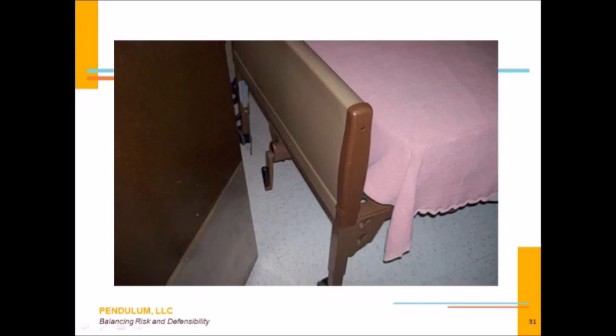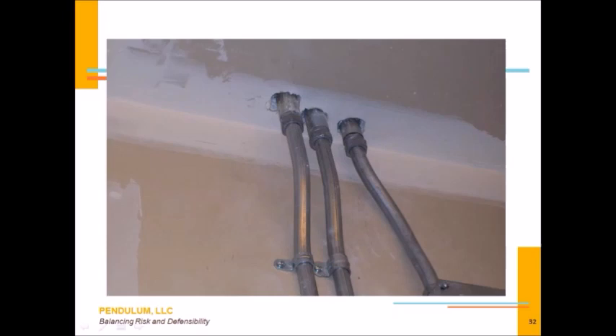Make sure all those items that are in the swing path to resident doors, to patient doors, or even to the cross corridor smoke and fire doors, there should be nothing within the swing path of those doors, to make sure that they close and a positive latch occurs where a positive latch is required to safeguard the spaces within your healthcare facilities.